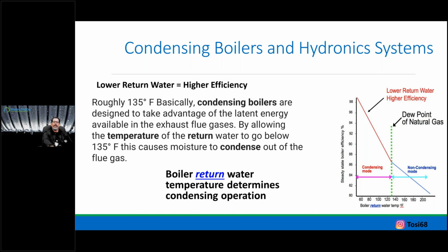So see where you can, again, envelope over equipment, heat loss, size up your emitters, and start understanding lowering water temperatures. And really, as you see the line here, that green dotted vertical line, the dew point of natural gas is roughly about that 135. So the lower that you continue, and this is maybe where outdoor reset comes in, taking advantage of having something outside telling the programming, hey, you don't need to be in high fire, you could be in low fire. So now we're really starting to collapse and condense and take advantage of that higher state of high efficiency. So you can see there the condensing mode, 135, is best to be to the left.